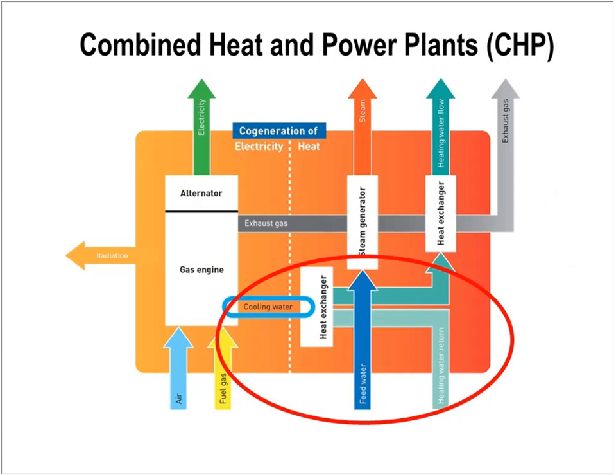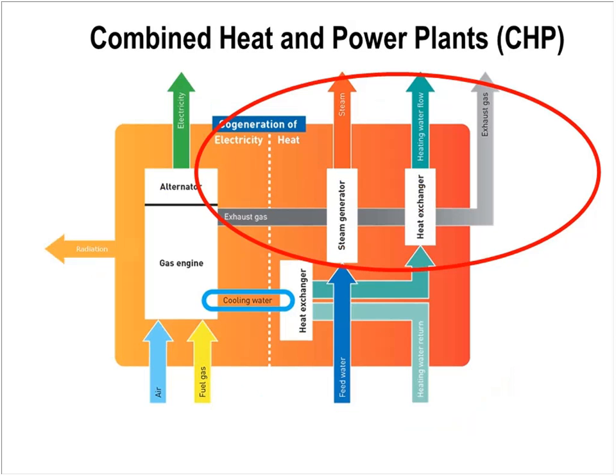Keep in mind that the cooling system's number one purpose is actually cooling the generator set - it is not the combined heat and power. So you need to pay close attention to make sure the engine is being cooled at all times, because if the engine doesn't work, you won't have either power or heat. So it doesn't make a whole lot of sense not to do that.